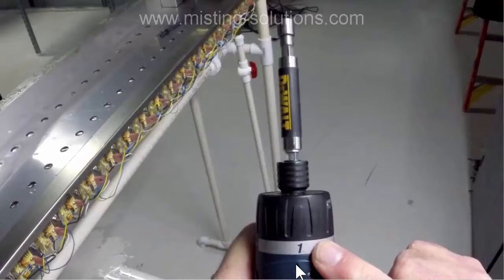This Bosch drill is very light on its number 1 setting. It hardly gets tight at all, which is actually ideal for lightly setting the nuts back onto the transducers without pulling them down too tight, because they're not supposed to be pulled down very tight. I've worked with other drills that are too strong and pull them down too tight. Not that it hurts anything, but it just doesn't need to be that tight. So the Bosch is a good unit for this job because it barely has any torque at setting number 1, which is just what I want.